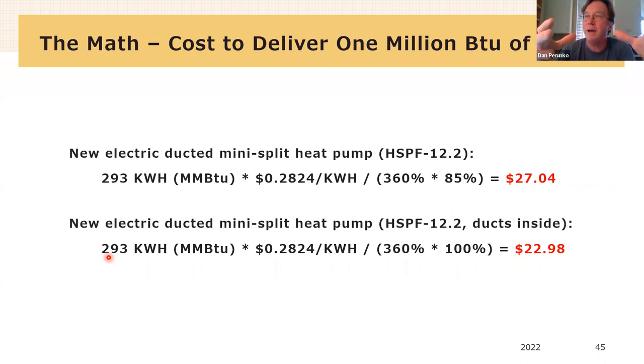Like when we have ducts in an attic, when we lose heat from the duct system, it's lost to outside the house. When we have a duct inside the house, when we lose heat through the duct, it's lost to inside the house where we were trying to heat anyway. So we get this initial bonus where we go from 15% losses to no losses if we can bring the equipment inside the house. And with the mini split ducted systems, this is becoming more and more possible. And I'll show you some pictures.